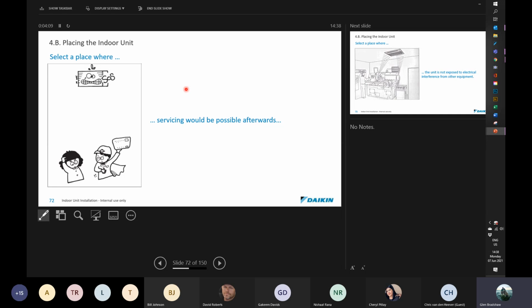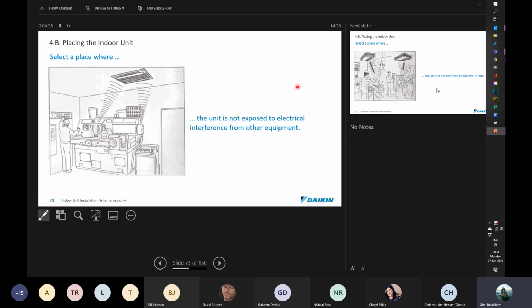The other thing to remember is that servicing is possible afterwards. We've always got to think of that poor guy that's got to come along and service, and he's often the guy that finds out that you can't get to the filters or to the drain pipe when there are issues. So those things should be taken care of at the installation of the unit. I know it's a difficult thing on some installations, but they need to be spoken about and documented if you feel that they're going to be an issue, so that when they do come around, nobody can say, oh, but you didn't tell us.